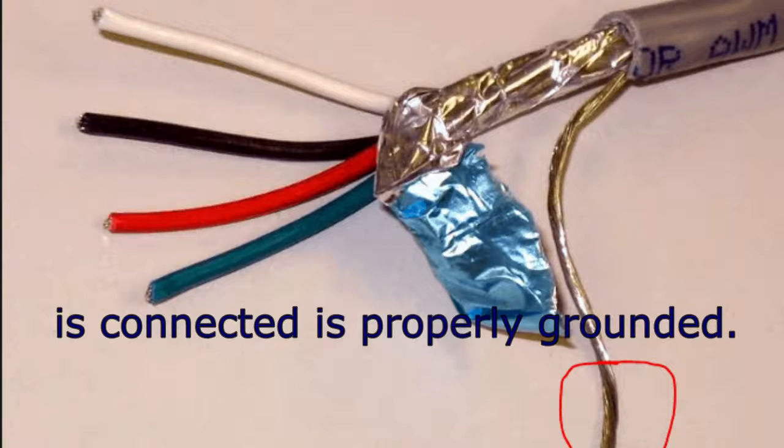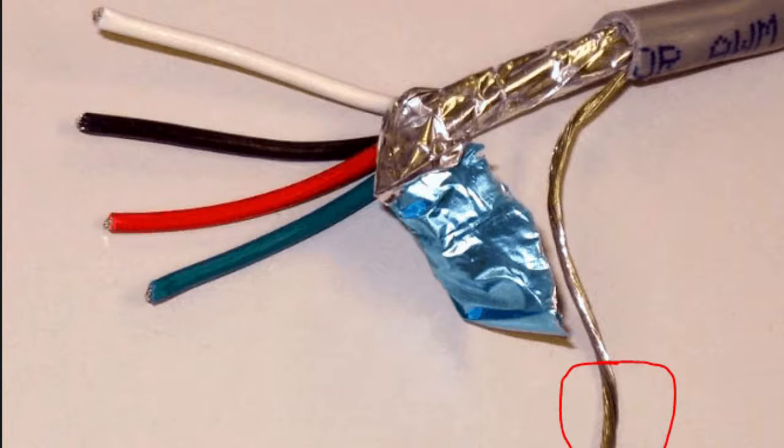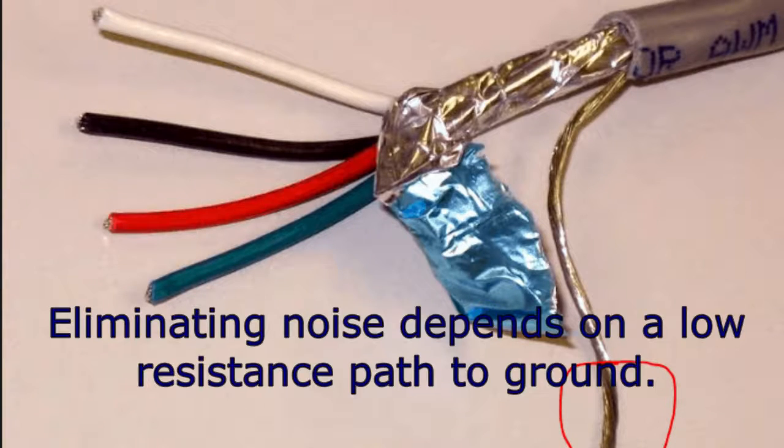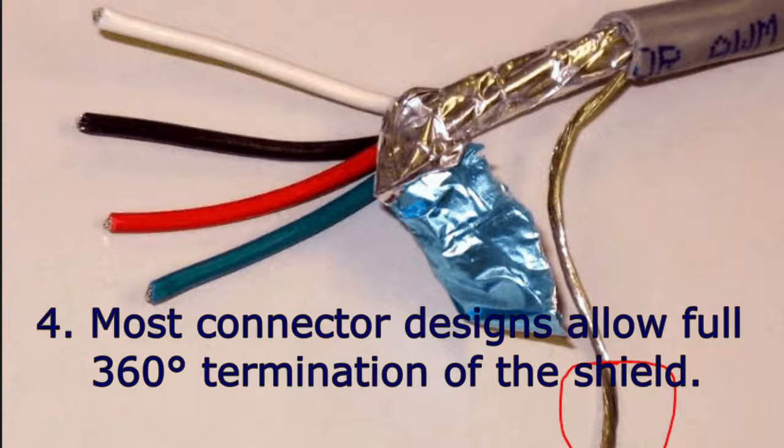Three, make sure the equipment that the cable is connected to is properly grounded. Use an earth ground wherever possible and check the connection between the ground point and the equipment. Eliminating noise depends on a low-resistance path to ground.